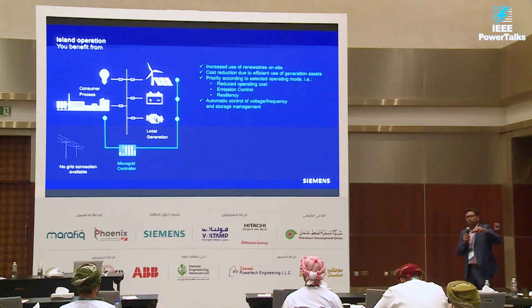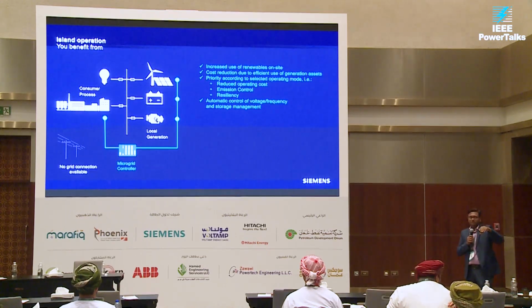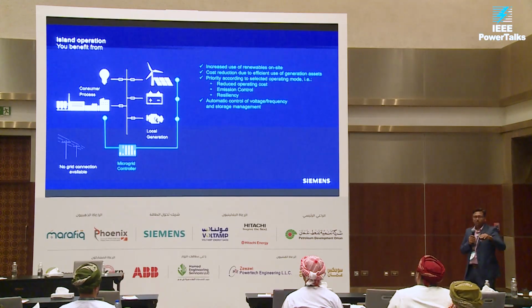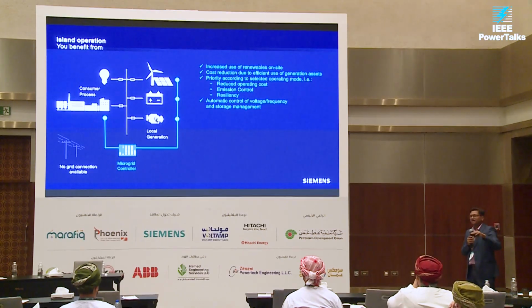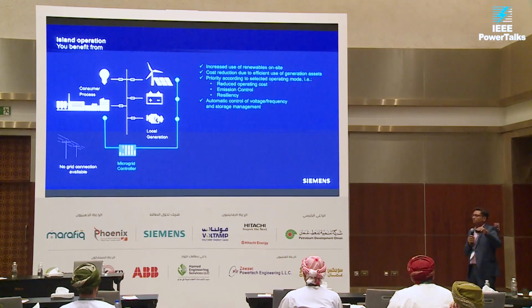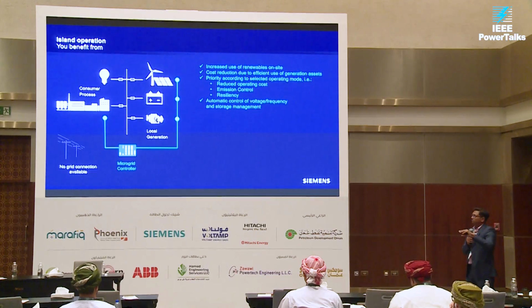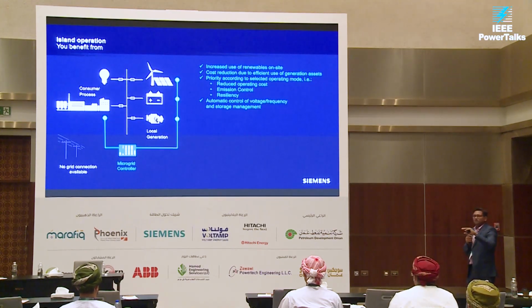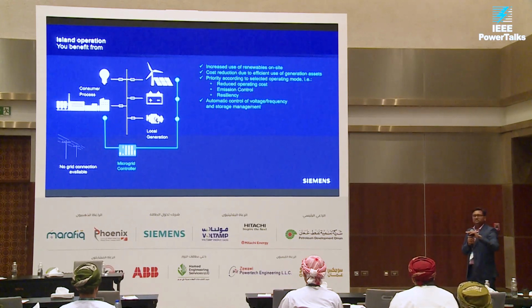There's always a minimum battery level that must be maintained, because the battery is the asset that forms the grid — in blackout conditions you really need at least some power reserved. Below that critical point, all loads get shed so the battery retains that essential power. So with a microgrid controller, you have the facility to manage all your assets based on your own priorities, and you can change that logic anytime.